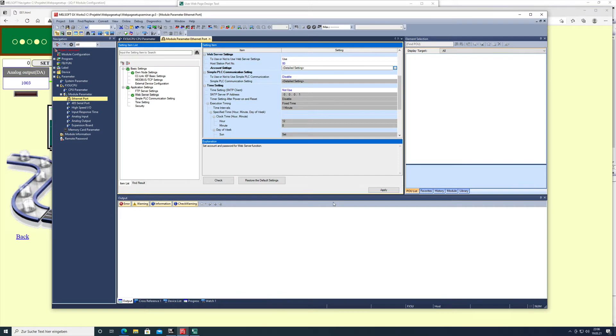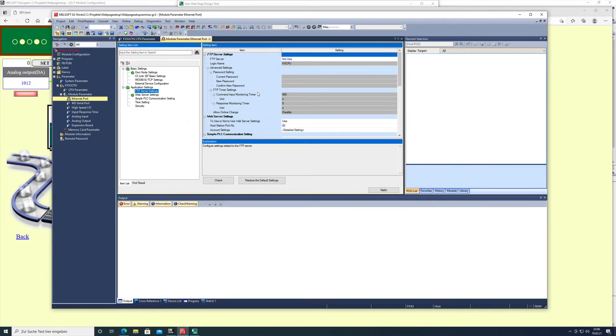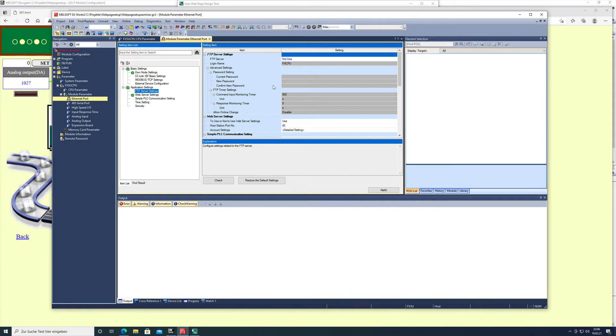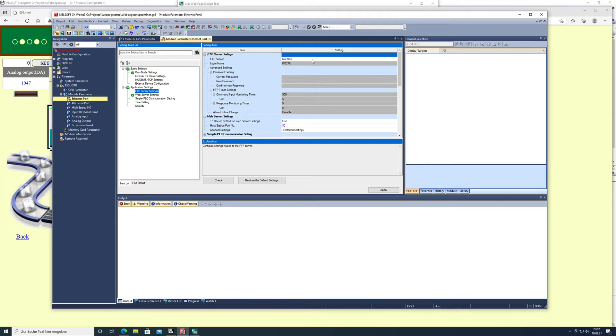Press OK, and you're all set on that. For the last requirement, you need to set the settings for the FTP server. The FTP server is necessary to write the data created by the user web designer tool in order to put that on the SD card. You need to put this SD card into the FX5 CPU. The website will not work without an SD card.